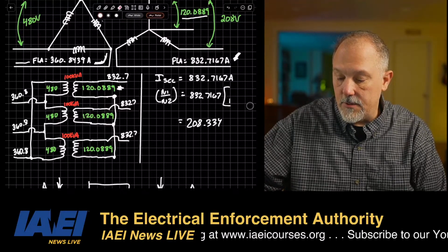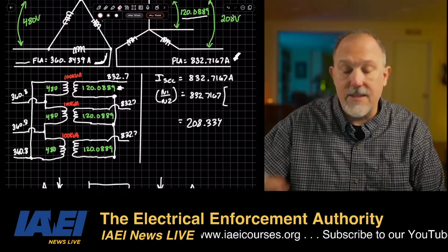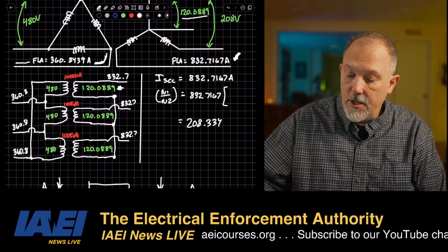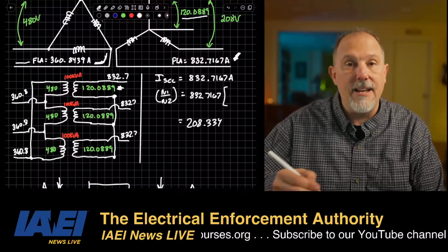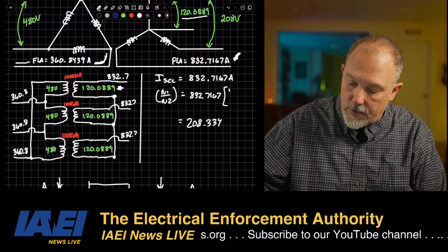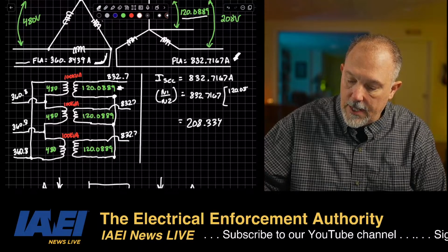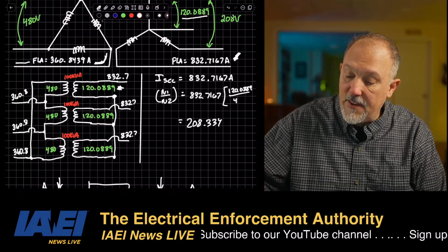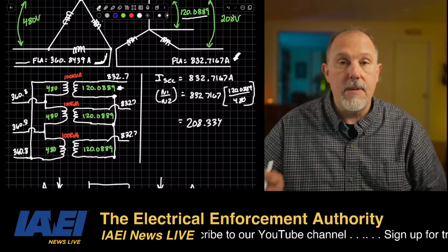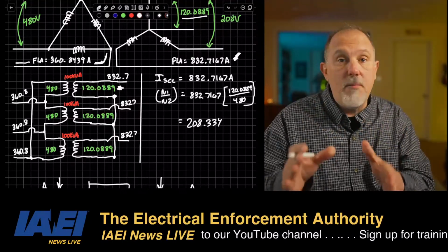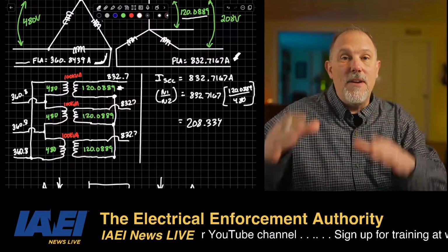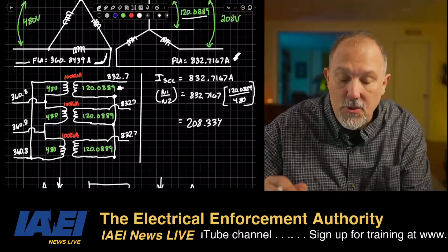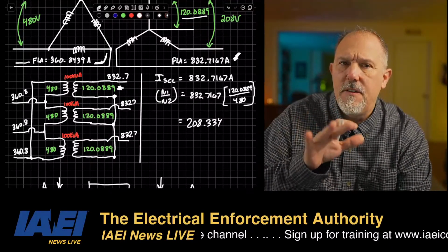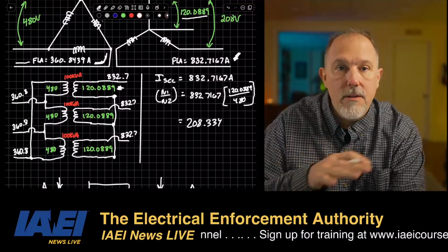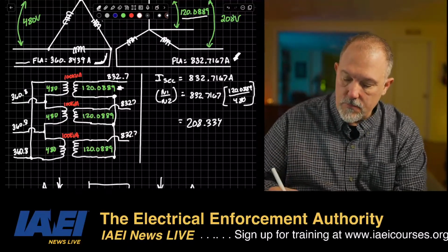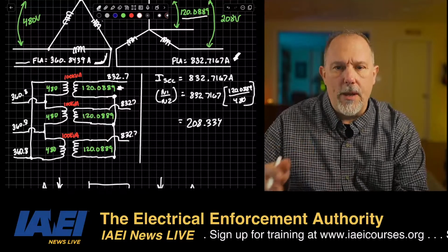I got this backwards. I want to reflect secondary current to primary. So I've got to take my secondary current times my secondary voltage, 120.0889, divided by 480. Make sense? And I'm using the 120.0889 because I want the numbers to match. I could use 120, but I'm going to be off by decimals. Not a big deal, but by decimals. And I'll run that real quick to show you.